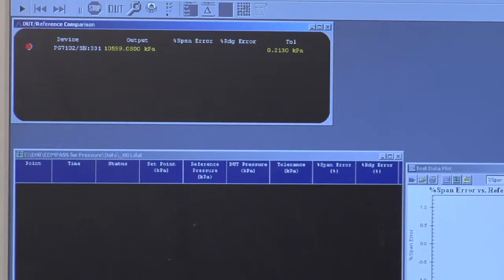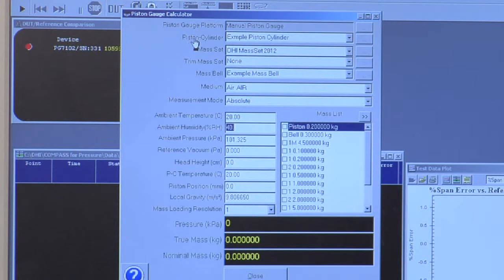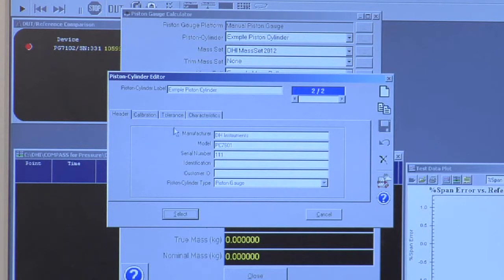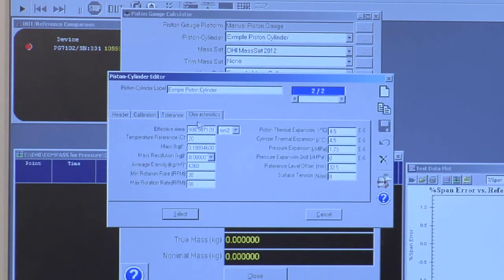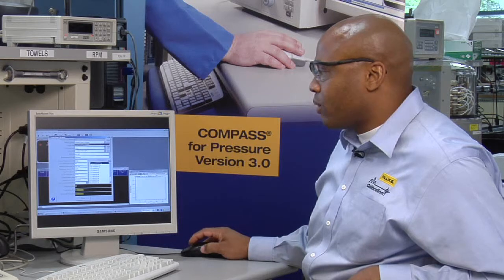Manual piston gauges are controlled by using the piston gauge calculator. You can customize all the elements used by the piston gauge, including the piston cylinder. The effective area characteristics are all defined on the characteristics tab. Any piston gauge platform can be defined with any number of piston cylinders.